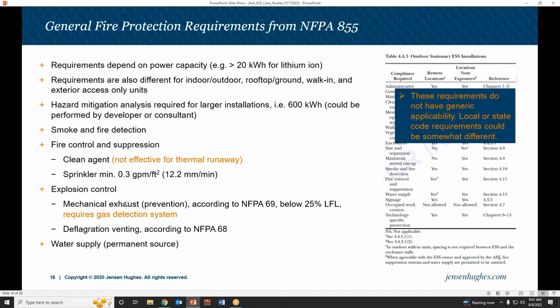Explosion control is required, either with a fan that would pull out the flammable gases once they're detected, or with deflagration venting — those panels that blow open. I think deflagration vent panels are a fine option if the system is not inside a building, maybe in a container, because we have a pretty good idea of the integrity of a container, so we can size those panels accordingly. But a building doesn't take pressure well — put half a PSI on a door, it'll blow the door out. So on a building you would need an exhaust ventilation system.